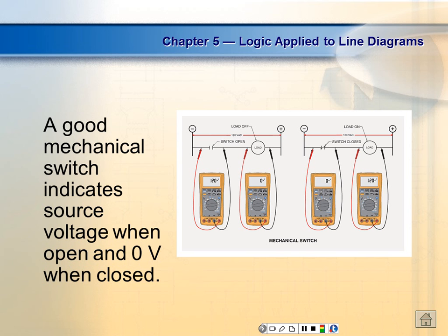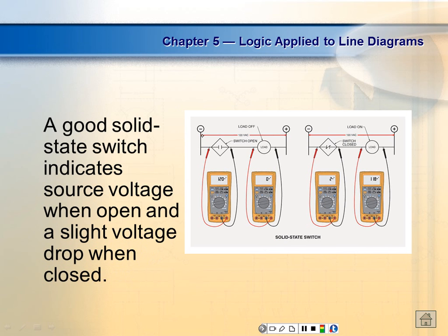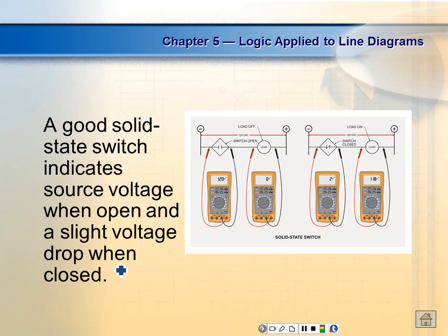Shorts in a series circuit are pretty easy to find. You just find a device that's not dropping any voltage, right? So you'll have 120 volts on one side and 120 volts on the other. By the way, if you want to check the fuse, so let's say we had a fuse right here, you don't want to do it with power off. And this is what we had to do on that crane box, by the way. We had to check it with voltage. Couldn't check it with an ohm meter, because if we checked it with an ohm meter, it broke the fuse.